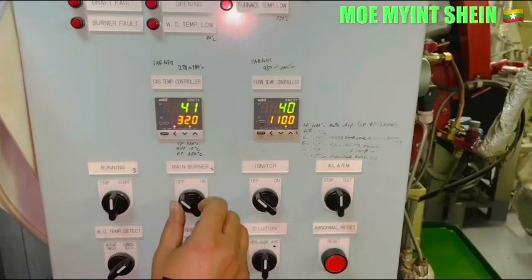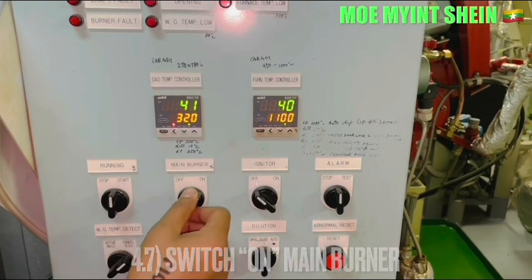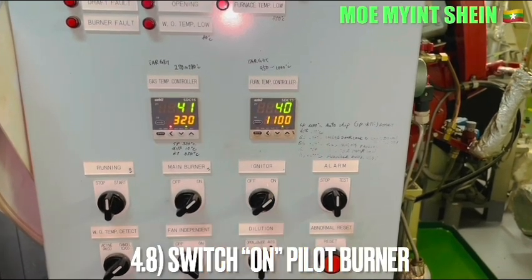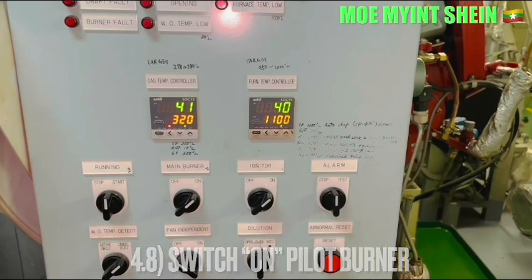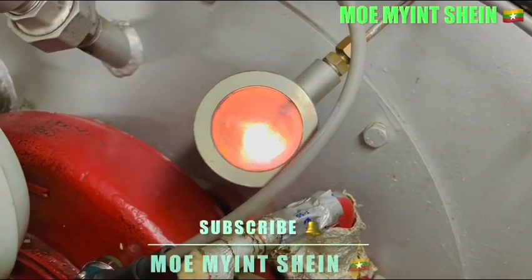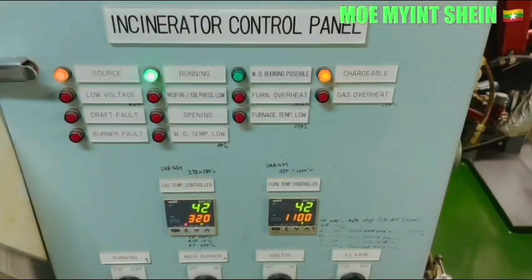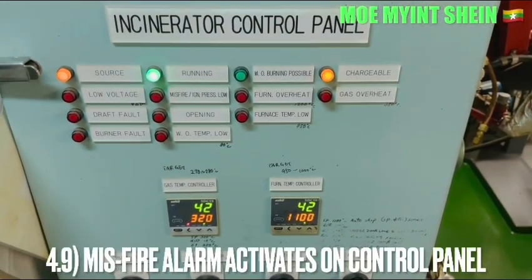Start running the incinerator and ensure that the forced draft fan is running. Switch on the main burner and igniter. Firing occurs inside the furnace or incinerator, but the misfire alarm will activate because we disconnected the socket of the flame sensor.